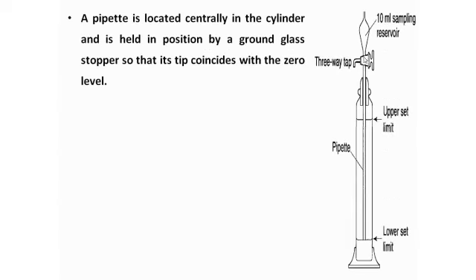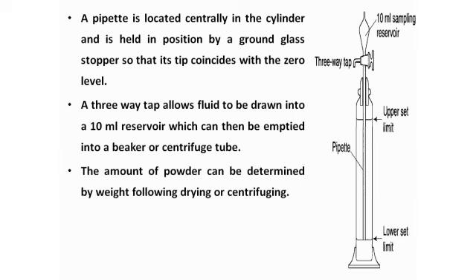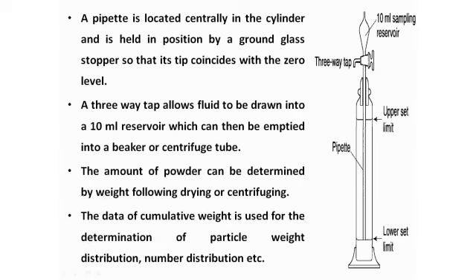A pipette is located centrally in the cylinder and it is held in position by a ground glass stopper. The tip coincides with the zero level. A three-way tap allows the fluid to be drawn into the 10 ml reservoir which can be emptied into the beaker or centrifuge. The amount of the powder can be determined following drying and centrifuging. The data of the cumulative weight is used for determination of the particle weight distribution and number.